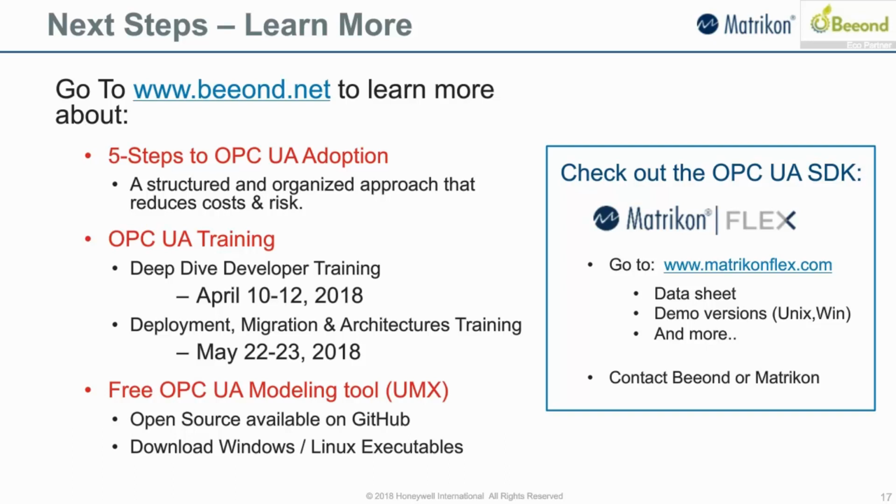Now, that's for applications that are native to a particular product, i.e. embedded within it. If you are talking about creating an OPC server that's going to talk from an external point of view to a third-party device or just from outside the device, then yes, you would actually have to have the protocol, or you would have to define how you natively talk to it.